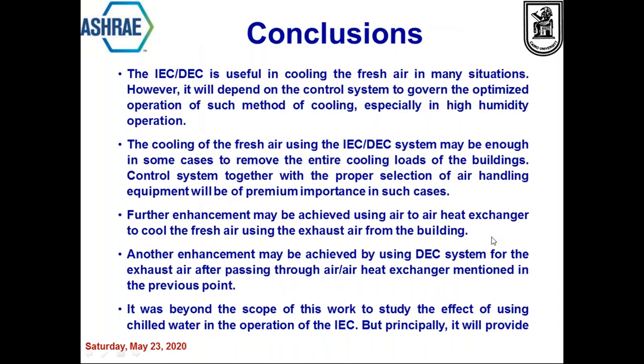I'd like to conclude. Indirect evaporative cooling is a useful cooling process for many situations, but it depends on the control system for optimized operation, especially in high humidity operations. Cooling of fresh air using indirect or direct evaporative cooling may be enough in some situations to remove the entire cooling load. What about if we design an air handling unit to reduce the outdoor air coming into the unit, the fresh air, down to 26 degrees centigrade and humidity of 50%? In this case, I will not need any additional cooling.